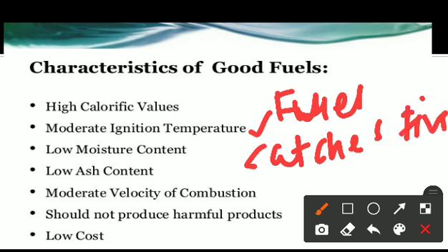It is called ignition temperature. It is also called ignition point. The value of ignition temperature decreases due to the presence of moisture and foreign material. If the ignition temperature of the fuel is low, it is easy to start fire, but it is dangerous for the storage and the transport.